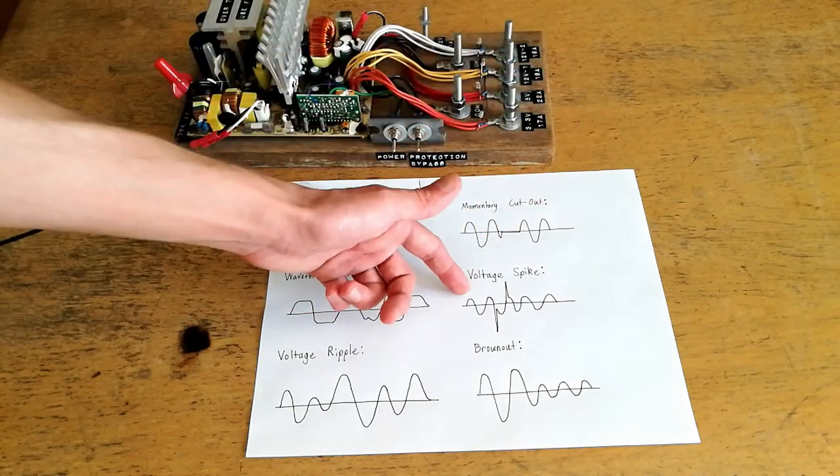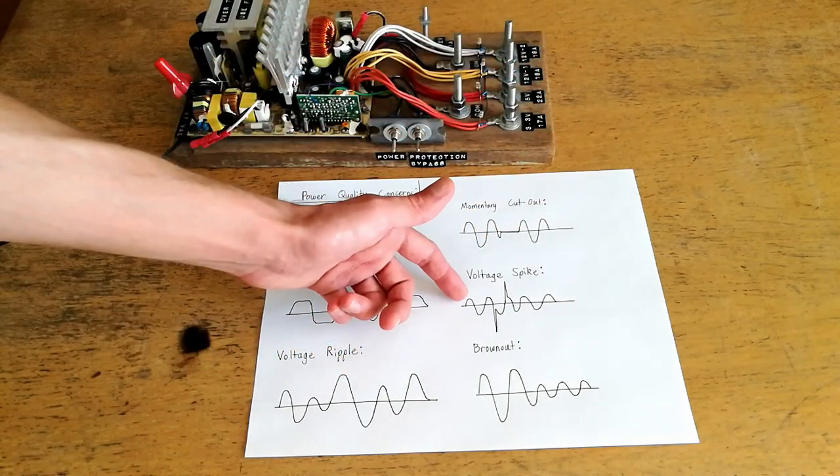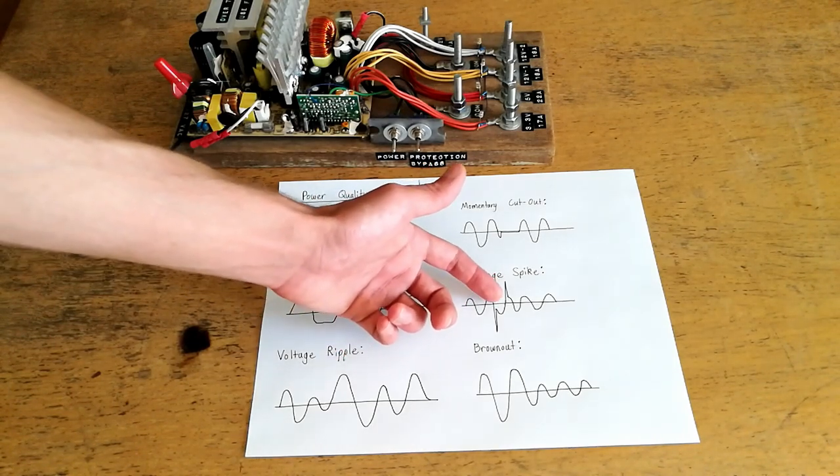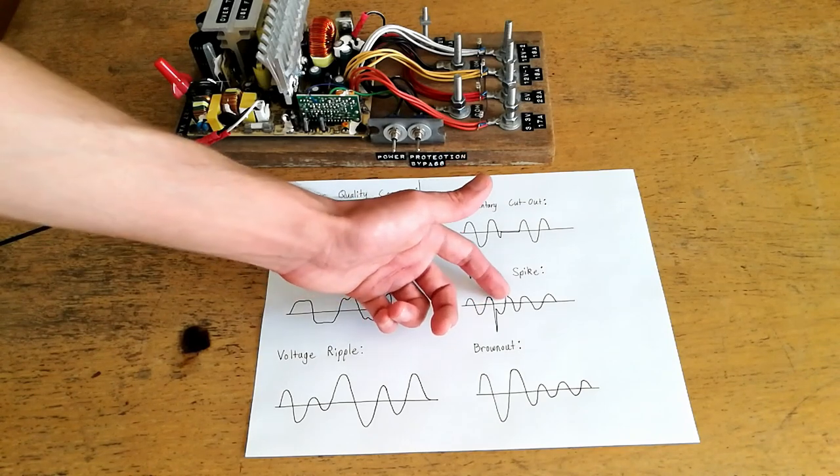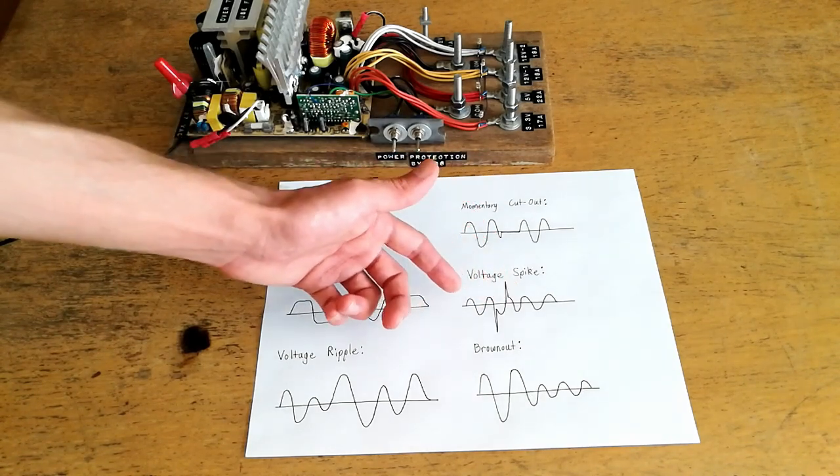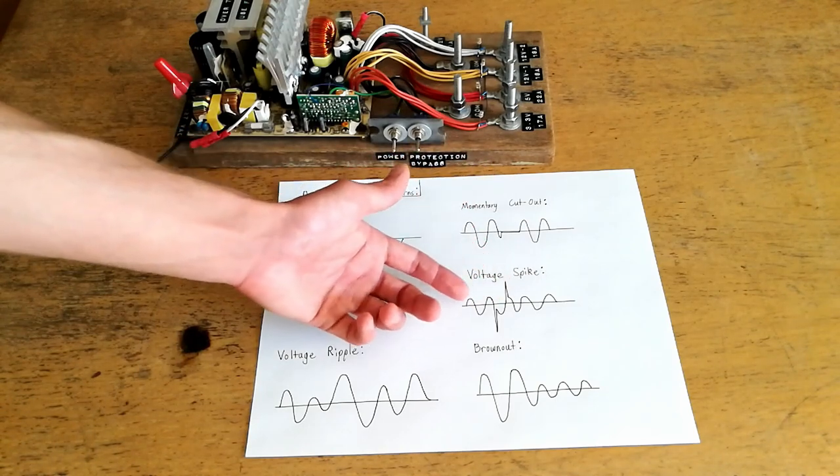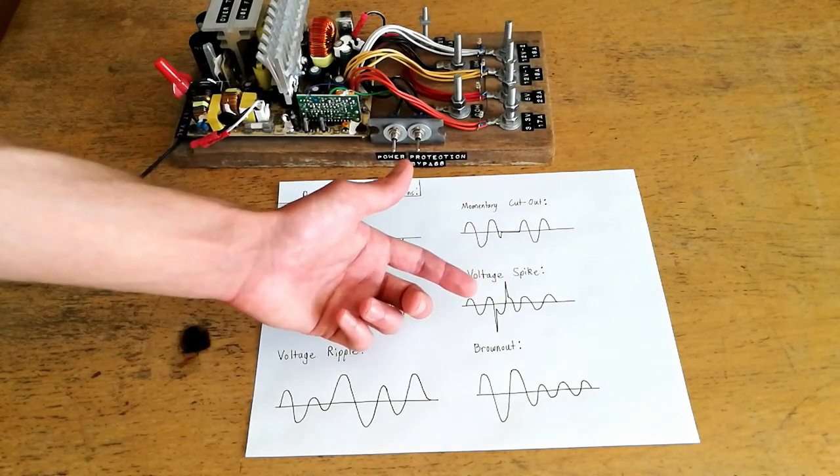Another problem that's similar to voltage ripple but somewhat more pronounced is voltage spiking. This can happen when there are large inductive loads on a circuit and they're suddenly switched off. That can lead to a sudden back EMF that raises the voltage substantially and this can result in potential damage to electronics or equipment that is not well filtered.